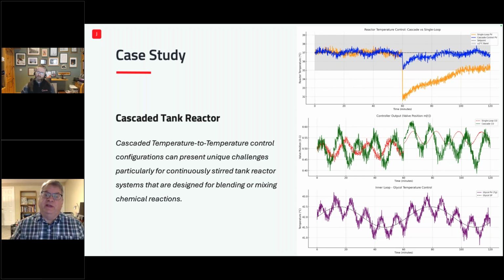So, it is modulating the set point. Do you see that, Damien? Yes, the set point at the bottom is modulating with the ebb and flow of that thermolator's temperature. The other benefit of cascade is that it shows you the other process variances that are in there, like that oscillation. Some of those oscillations wouldn't be evident when the disturbances are hitting so hard, because it's forcing the system to work. It's only when you calm down a system by using cascade that you can then take it to the next level and improve the set point tracking, or the outer loop control, or the more critical parameter, to give you that more stable control. That's a money maker for us. Yes, absolutely. And those bioreactors are very temperature sensitive. They really don't like the variance on it.